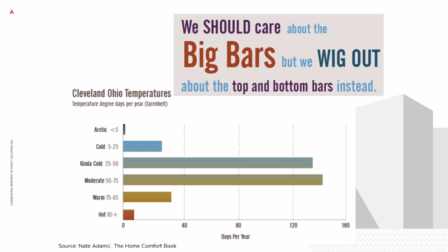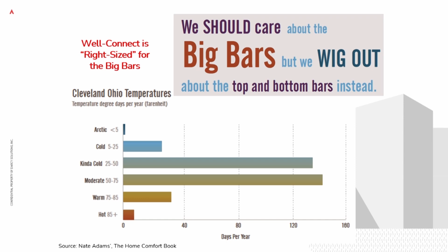When HVAC companies size a project, and we did the same thing, you size for the coldest days of the year and the hottest days of the year. But most of the time, based on data from Cleveland, it's not that hot and it's not that cold, it's only a handful of days a year. So the majority of systems are way oversized for what it's like most of the time. You build the church for Easter Sunday, but the rest of the days it's way oversized.